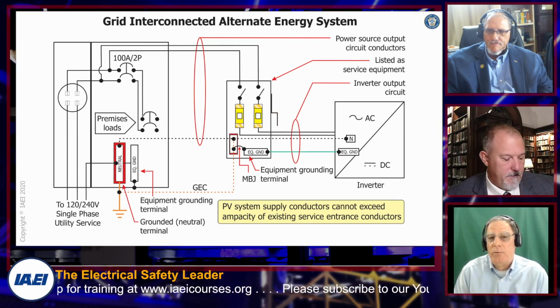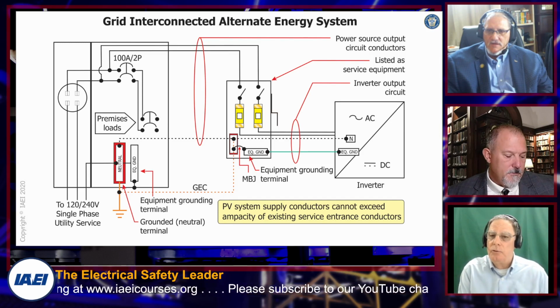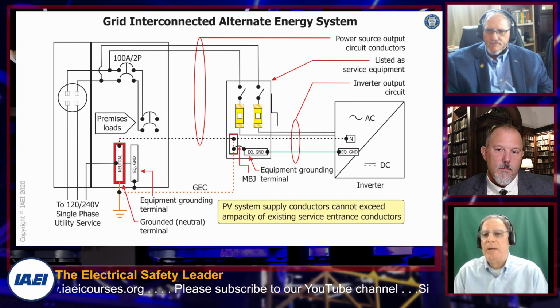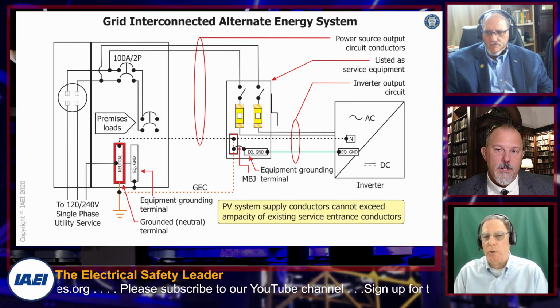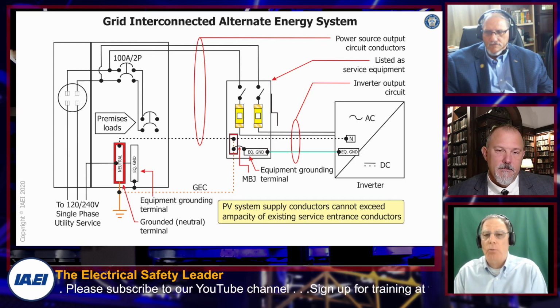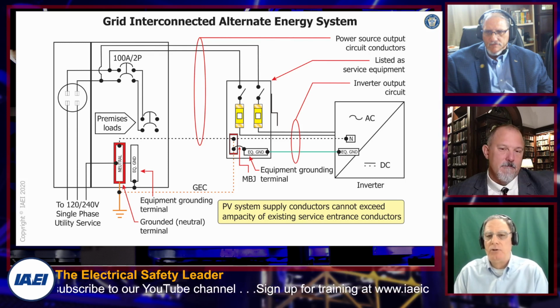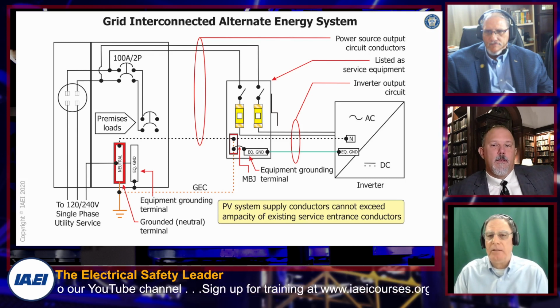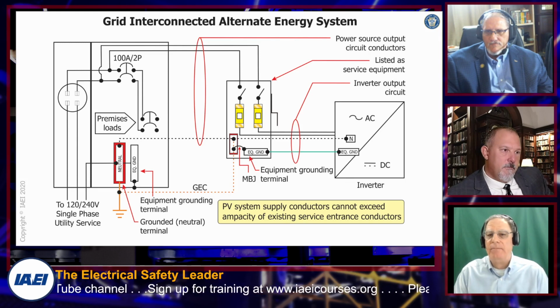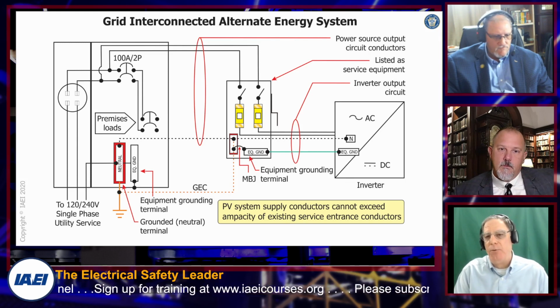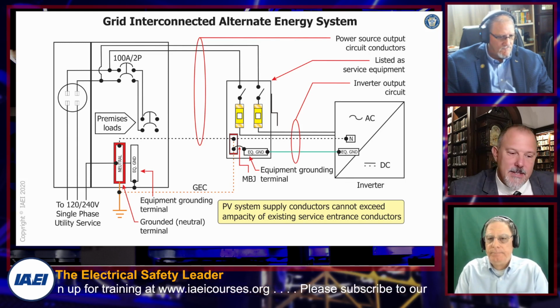And that's the big deal with grounding and bonding. You have to look at normal operation, and you have to think about abnormal operation. Right. The short circuit, the overload, the ground fault. What's going to happen? What wire is going to be affected? How is it going to be affected? And is it going to survive until the protective device operates? Yeah. And I just had this discussion.